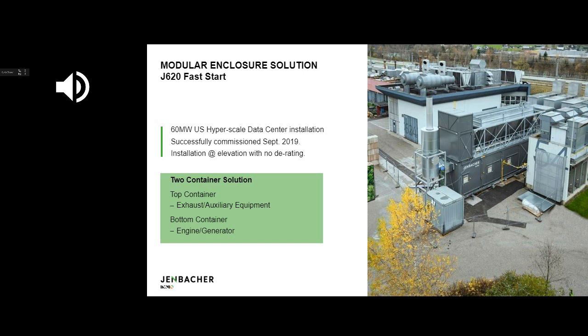One of our projects is a hyperscale data center in the U.S. using 20 of the fast start 3 megawatt units that Santiago touched on earlier. This is a factory packaged container solution to expedite installation and delivery, with high temp, high elevation installation without any de-rate in this application. No on-site fuel storage is needed, as discussed earlier, and the study has been completed — it's proven, field-validated technology.